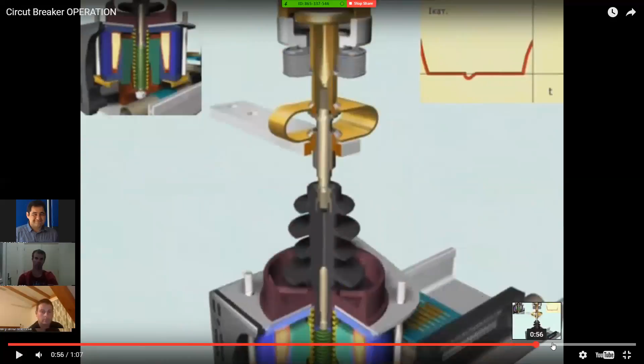Sizing circuit breakers is pretty much the same as sizing fuses: nominal current, nominal voltage, and maximum interruption capacity. But the difference is the breaking time, how the breaking works, goes to the protection. Why? Because it requires a relay to receive an order, so the circuit breaker isn't able to handle that itself.